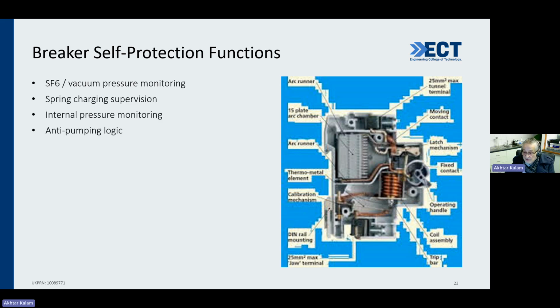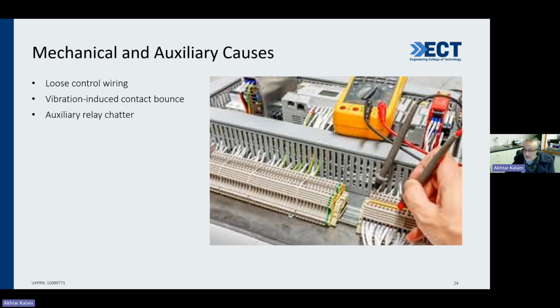Also, if you look at the auxiliary causes or the mechanical, remember I told you the mechanical device. There could be a loose wire, or the vibration could have induced a contact bounce, or the auxiliary relay could be chattering. And remember, it's a mechanical device. So you 14 people attending today's presentation might say, why should I bother? I'm an electrical engineer. My friend, in the field, you're not just an electrical engineer. You have to look at all facets. If there's a mechanical problem, think mechanically, my friend.